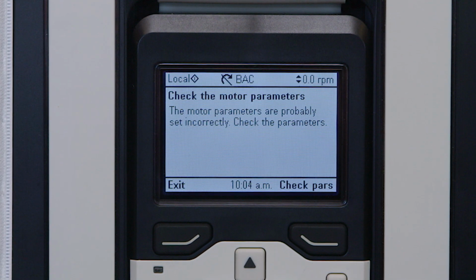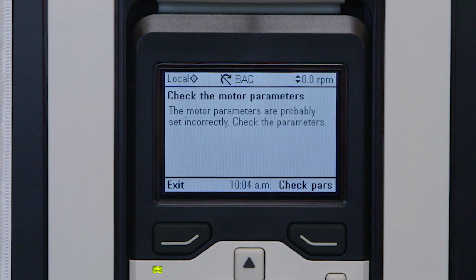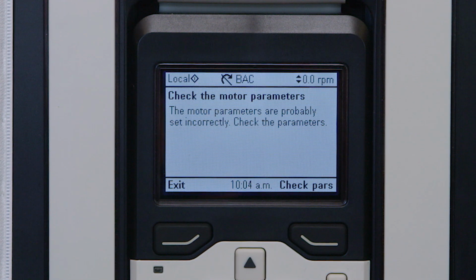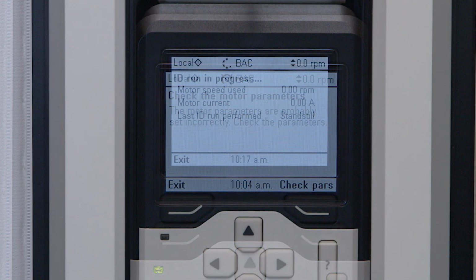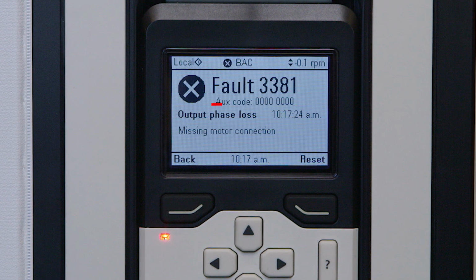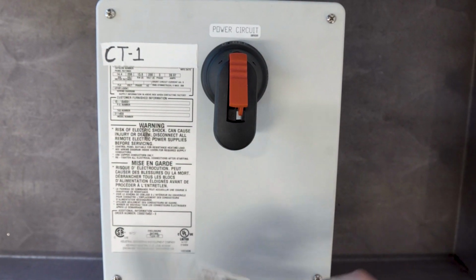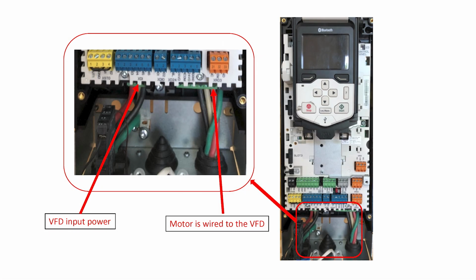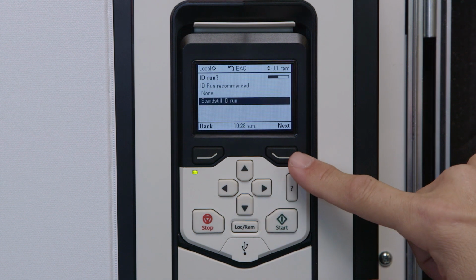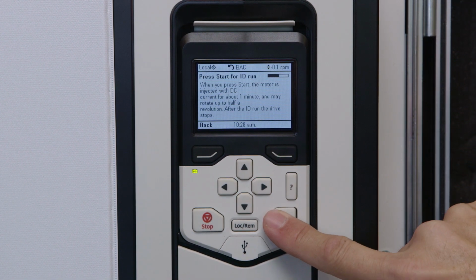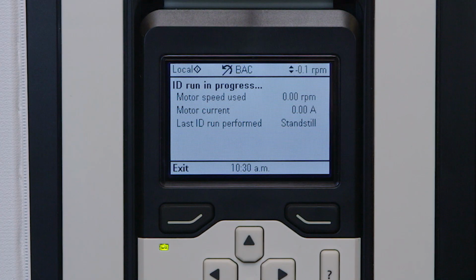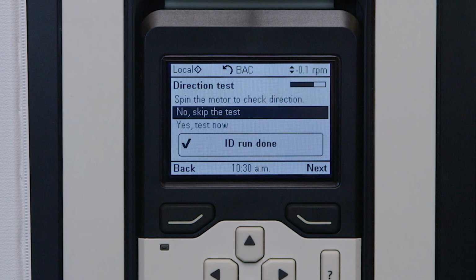But if you see the message check the motor parameters, then the ID run failed. An ID run fail may be caused by entering incorrect motor information. Check to make sure the motor data information you entered is accurate. If you get a red light fault that says output phase loss, this typically happens if the motor is not connected to the VFD or the tower disconnect is open. Ensure the lockout tagout is removed and that the motor cable is connected at the VFD. After you fix the issue that failed the ID run, you must reinitialize and repeat the ID run. You can proceed to the next step when the display exhibits the message ID run done.